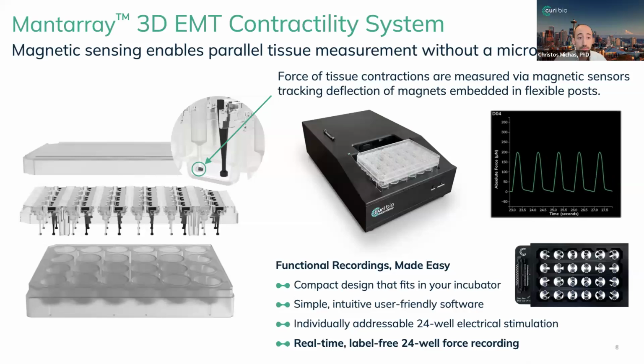And that black dot is a magnet. And when the tissue contracts, it moves the magnet. And so if we were to take the entire plate and place it on the Mantarray instrument, which you're seeing in the middle, the Mantarray instrument is equipped with magnetic sensors that can track the position of the magnets, all 24 of them, and in real time for all 24 tissues, present to you the contractile force of the tissues.